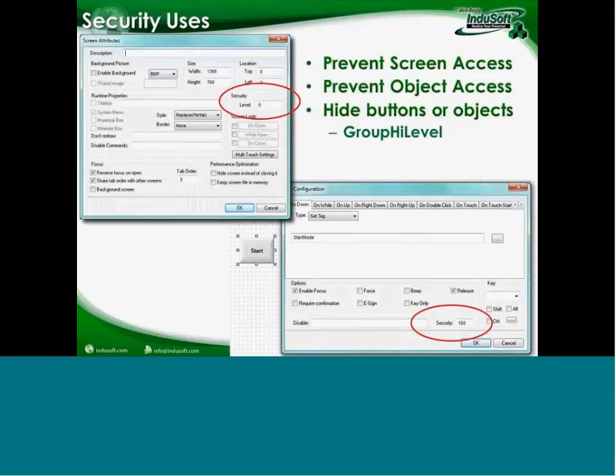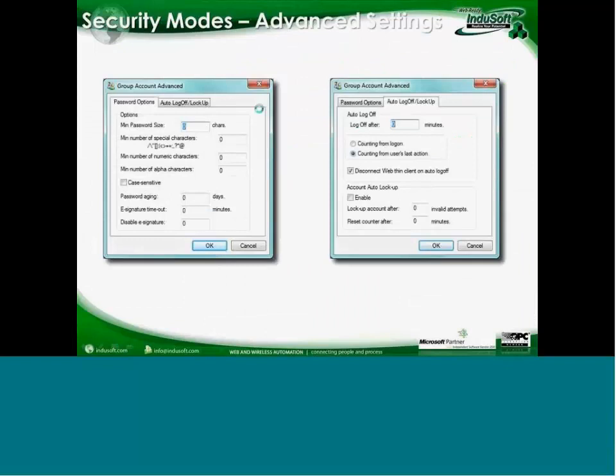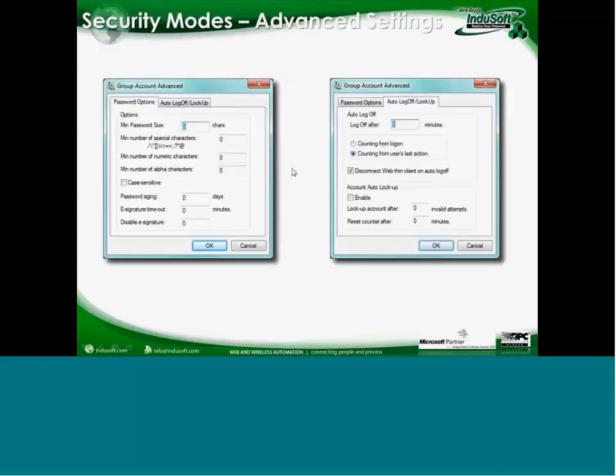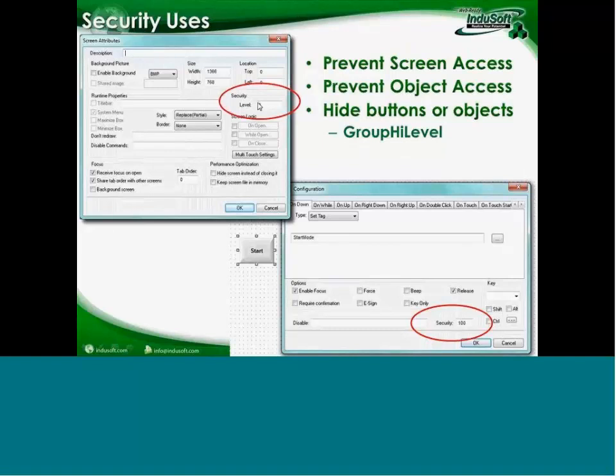One of the security uses is preventing screen access. In the screen attributes for any given screen, you can set a security level. In the group setup, you choose security levels independently for development and runtime — for example, an operator might have a range of 0 to 50, and a supervisor 0 to 100. You then use that security level in the screen attributes so only users within the allowed range can access that particular screen.